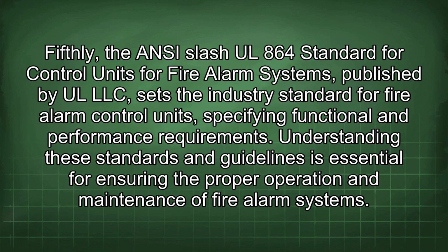Fifthly, the ANSI/UL 864 Standard for Control Units for Fire Alarm Systems, published by UL LLC, sets the industry standard for fire alarm control units, specifying functional and performance requirements. Understanding these standards and guidelines is essential for ensuring the proper operation and maintenance of fire alarm systems.